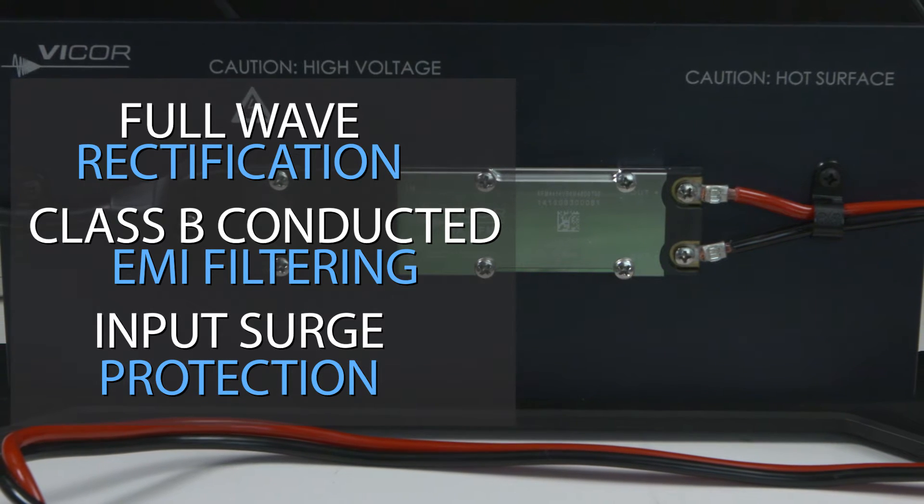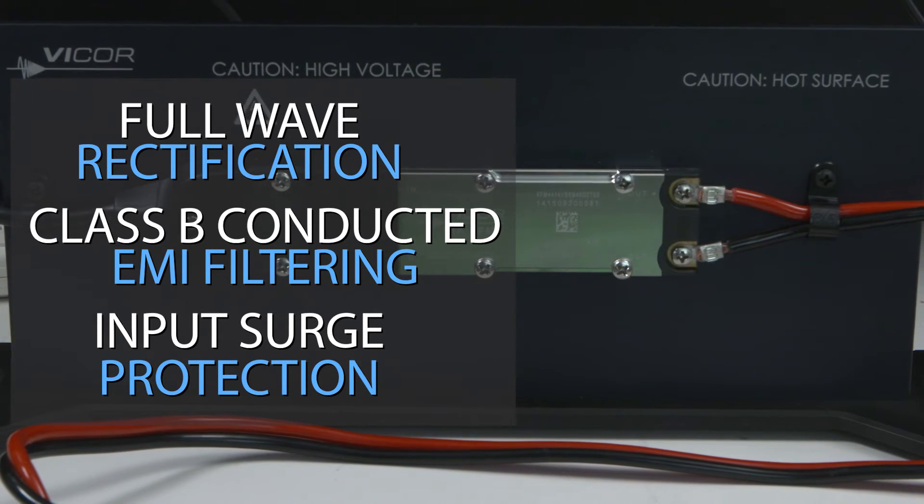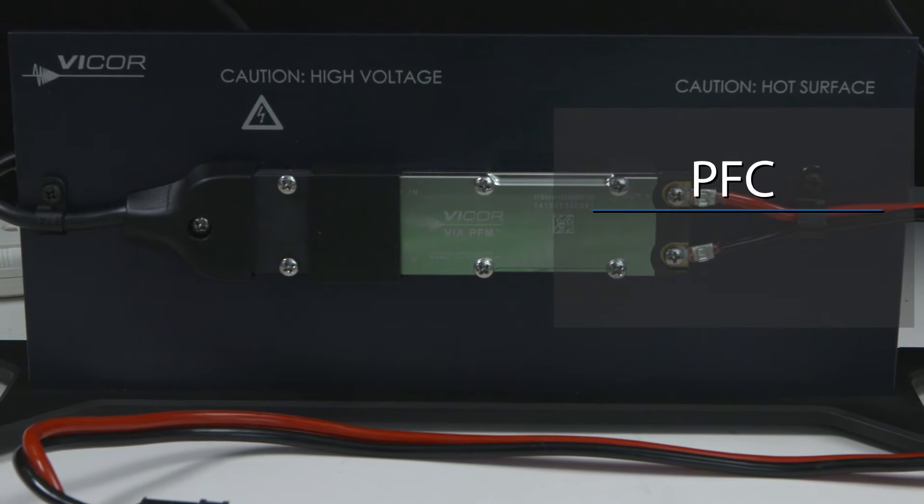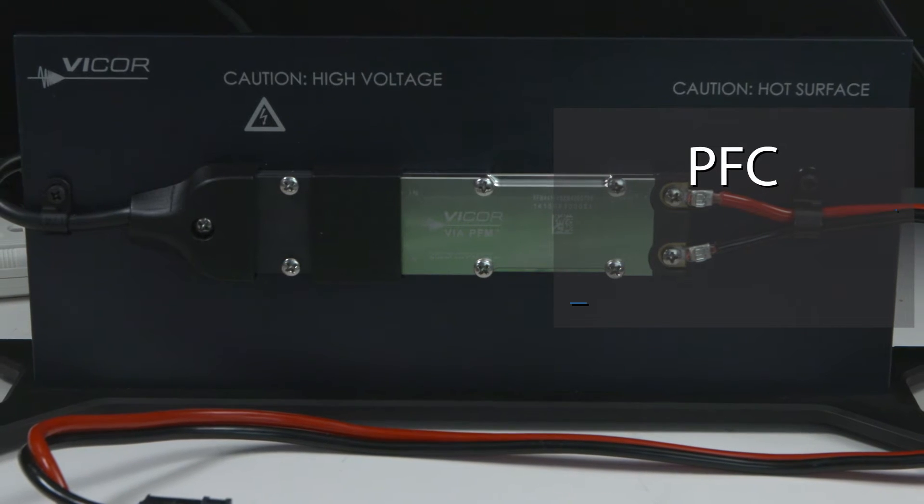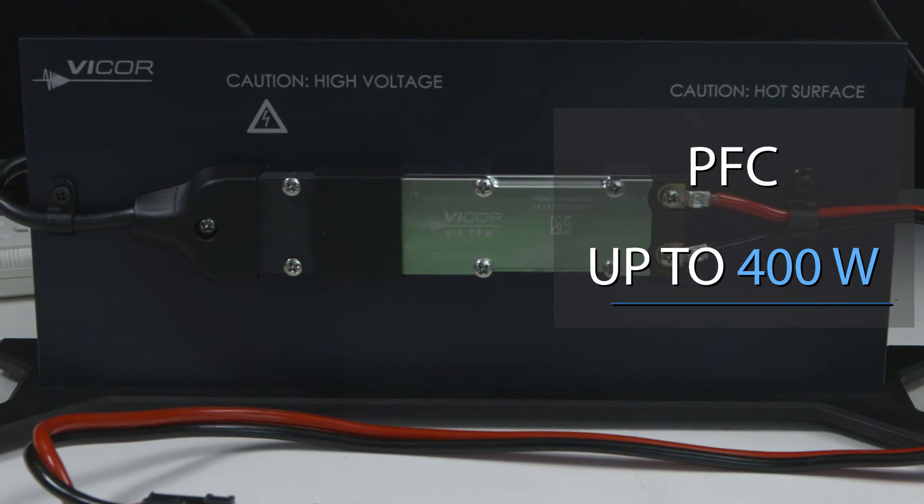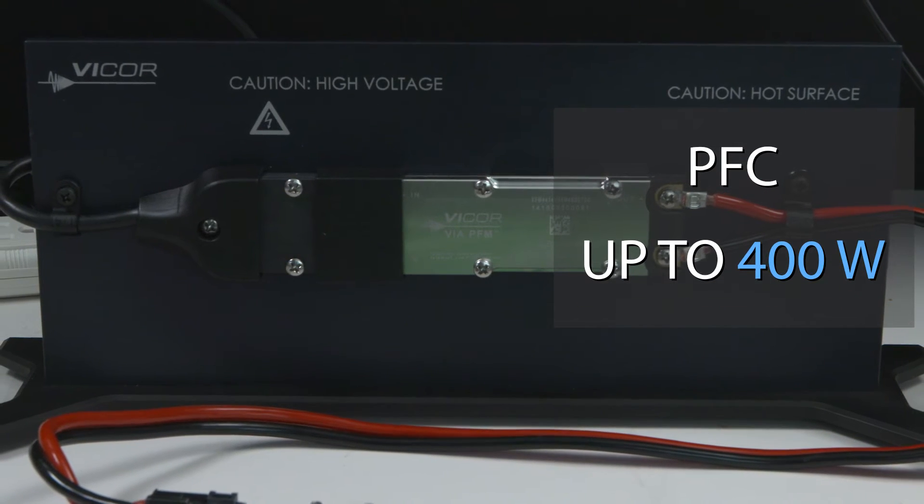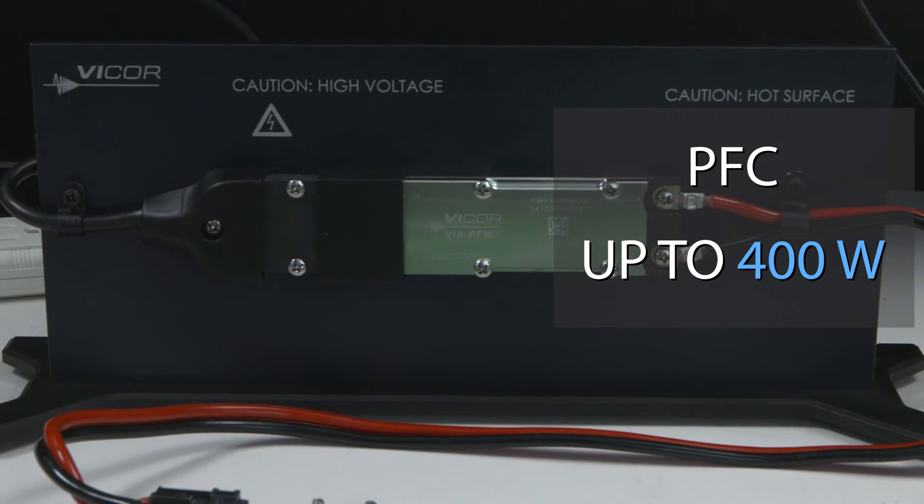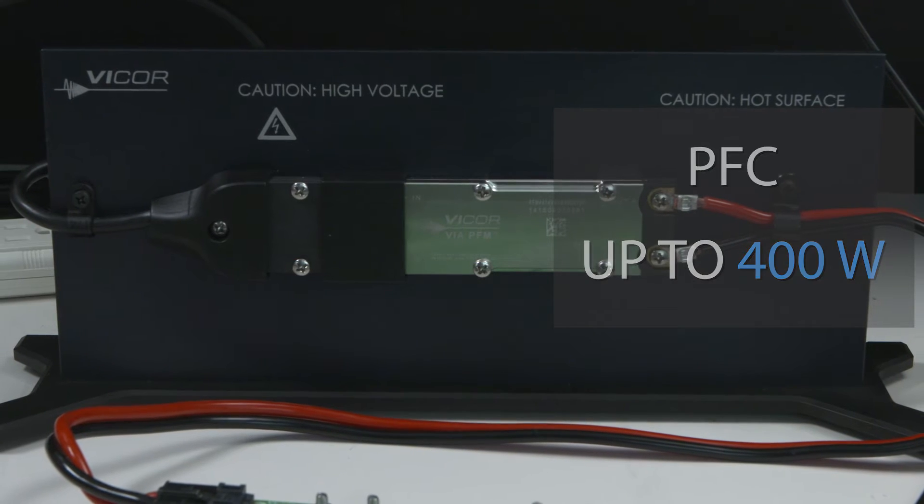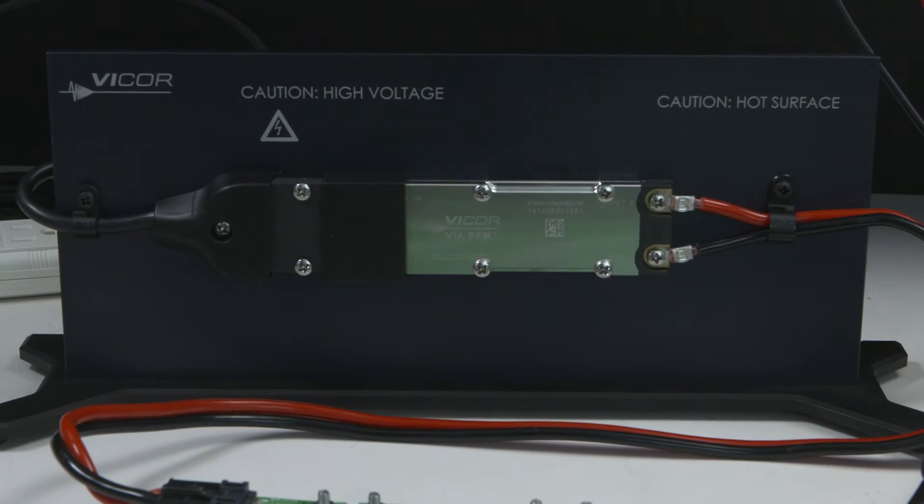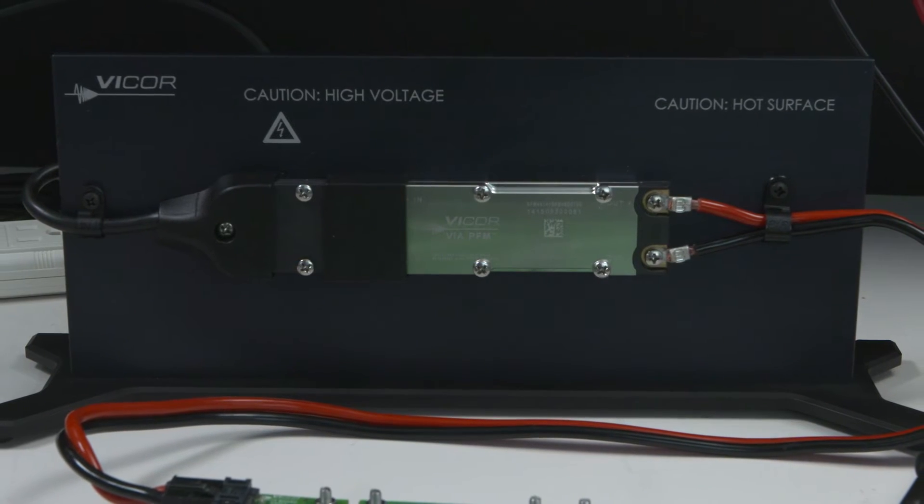The PFM, which receives its input power from the AIM, features power factor correction and delivers up to 400 watts of isolated regulated 24 or 48 volts DC for powering downstream regulators.